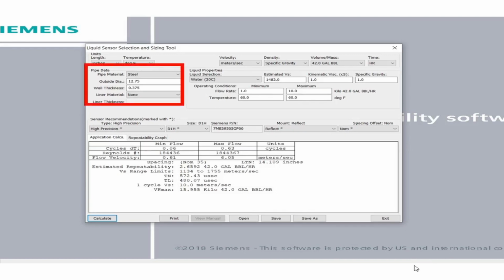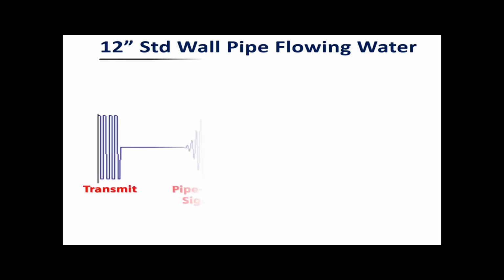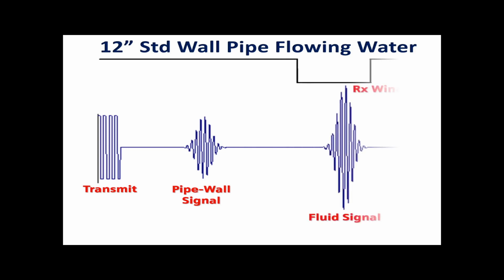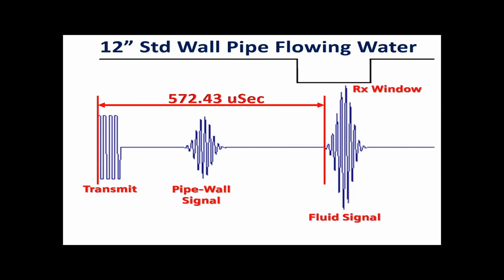Okay, all you liquid application people. Let's assume our pipe is a 12-inch standard wall steel pipe flowing water. The theoretical transit time for a reflect mount sensor installation using D1 high precision sensors is 572 microseconds. This is how long it will take for the sonic beam to travel from one sensor to the other through the fluid, and how the meter will position the RX window. The pipe wall signal will of course arrive much earlier and be electronically blocked.